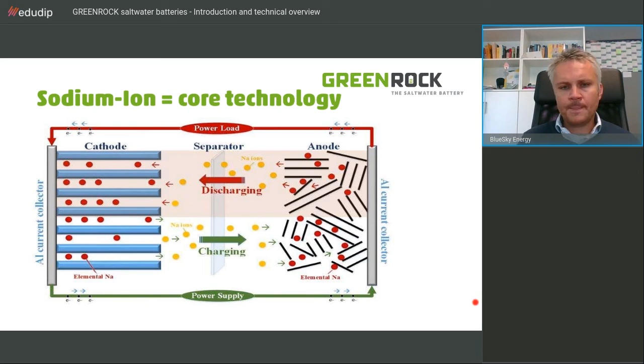In general, we have got two versions of that battery. One is the 48 volt version, which is a nominal 2.7 kilowatt hours with 4 amps charge discharge. We've got the voltage range of 35 volts to 59 volts. We are charging with constant current. The depth of discharge is 100%. Round trip efficiency is above 85%. The maximum charge rate and discharge rate is 20 amps. And temperature, as already mentioned, is -5 degrees Celsius to 50 degrees Celsius. Life cycles: 5,000 cycles at 80% DOD. So that's the 48 volt version.